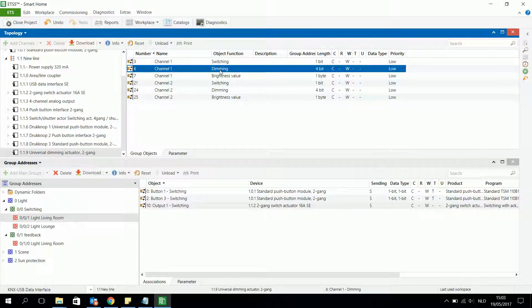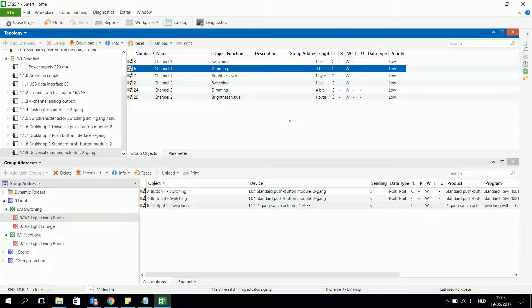First of all I have to program switching on and off the light with a 1-bit object, and also dimming up or down — darker or brighter — with a 4-bit object. So I need two different group addresses in which I will associate the two different objects with the objects of the pushbuttons.